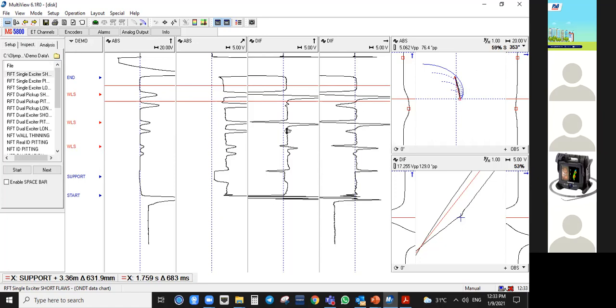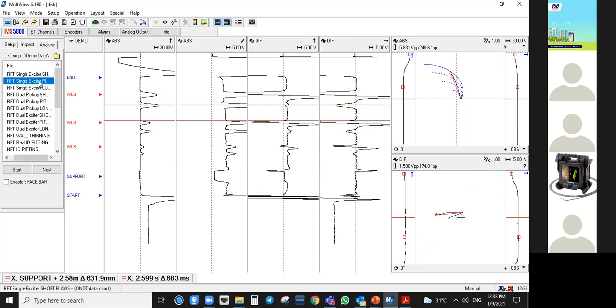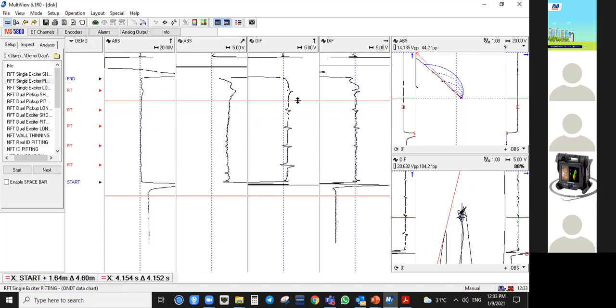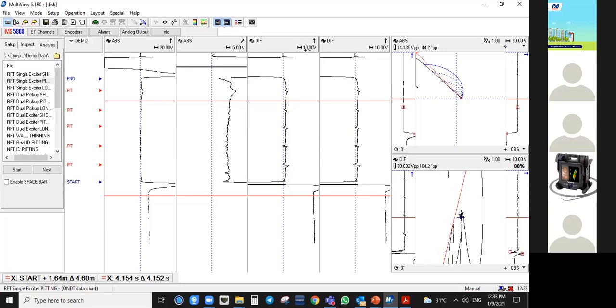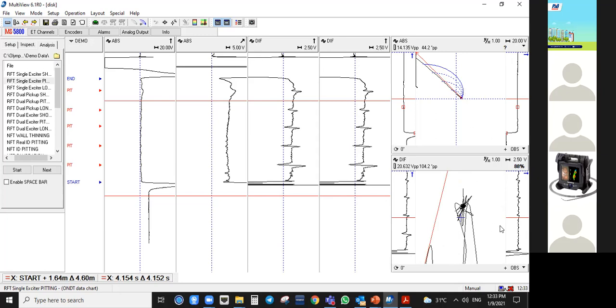Usually our calibration tubes have an OD defect that is 360 degrees. So it will show you here around 353 or 360 degrees separation, I mean wall loss, and it's 60% short. This is how we usually calibrate. When it comes to pitting, it's different. We don't use absolute strip chart to analyze the pitting, but we use differential. Just make sure you lower your voltage, and then you'll see it here on the differential.